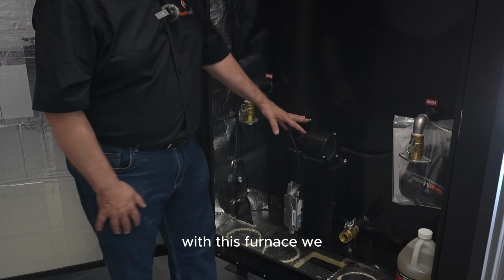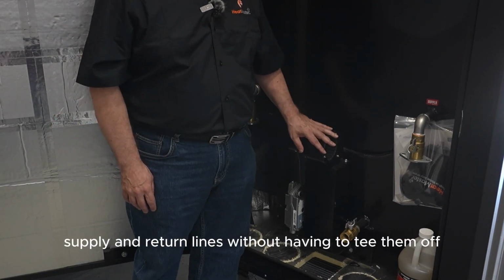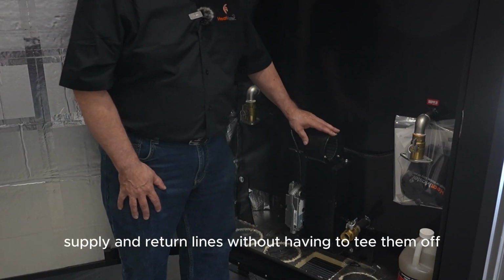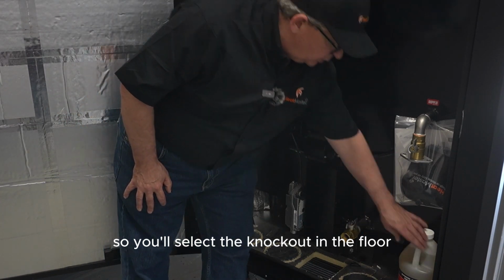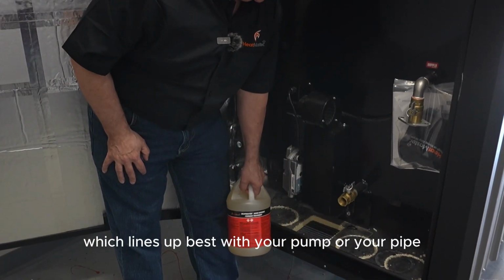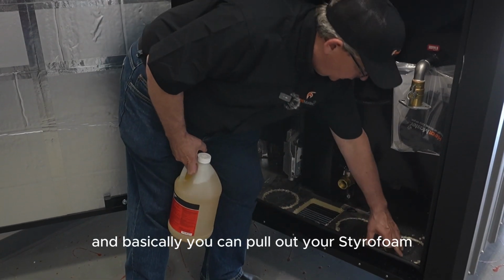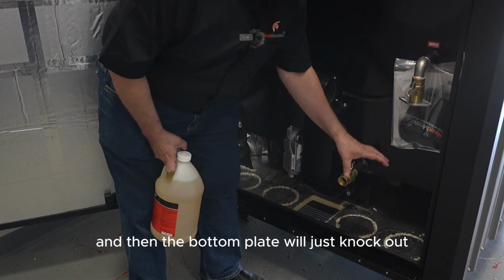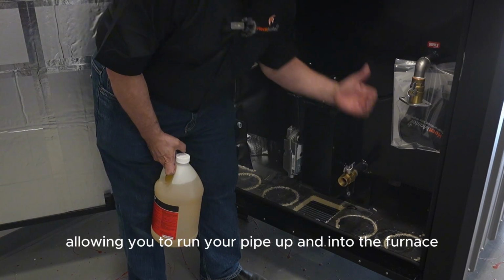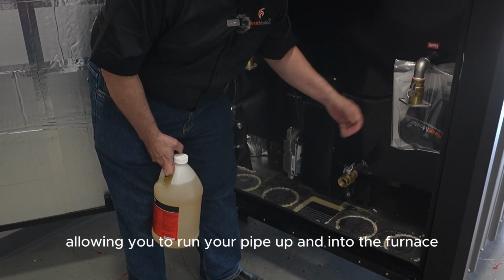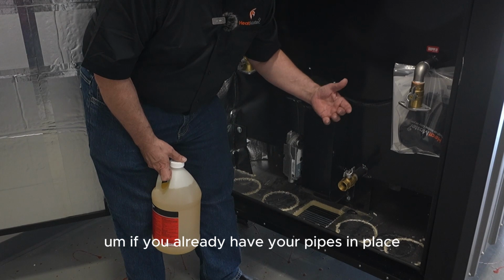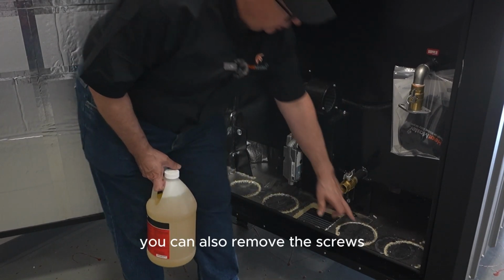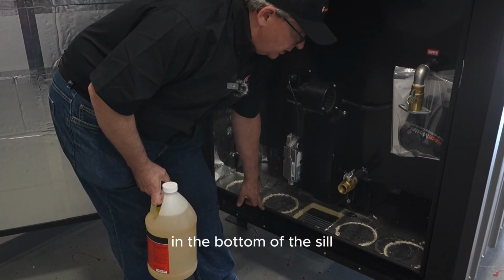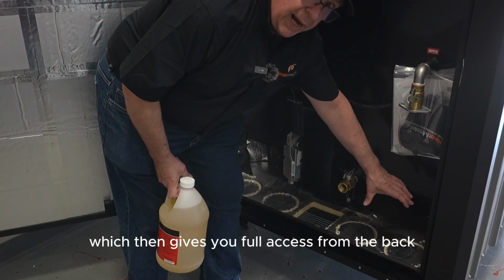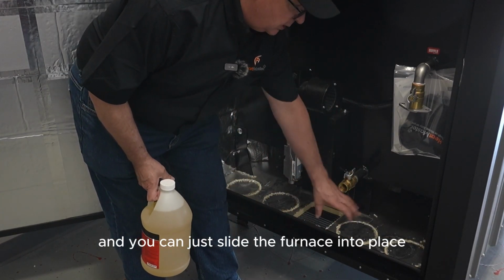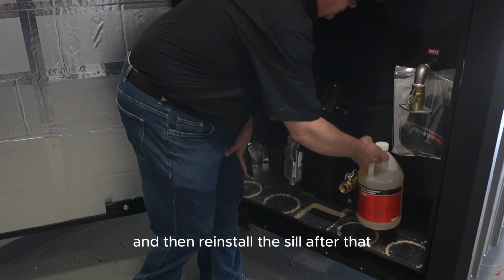When you come to the furnace, you'll notice there's a series of knockouts in the floor. With this furnace, we have the ability to run 2 different supply and return lines without having to tee them off. So you'll select the knockout in the floor which lines up best with your pump or your pipe. And basically, you can pull out your styrofoam, and then the bottom plate will just knock out, allowing you to run your pipe up and into the furnace. If you already have your pipes in place and you want to install the furnace, you can also remove the screws in the bottom of the sill, which then gives you full access from the back, and you can just slide the furnace into place and then reinstall the sill after that.